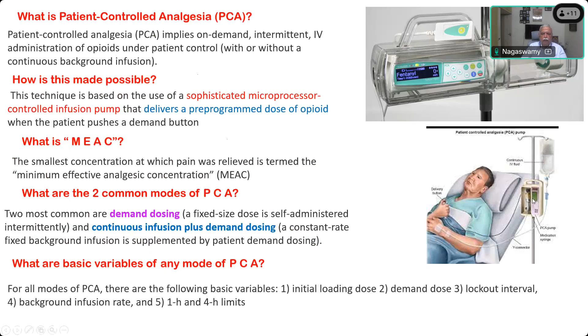What are the basic variables? That is the parameters that you have to include in the mode of PCA. There are five things which you have to think of. One is, what is the initial loading dose? This you have to calculate and then program it into the infusion pump. Then how much every time the demand dose you have to give, and what is the lockout interval, whether it is 15 minutes, 30 minutes or 1 hour, and what should be the background infusion rate, and what are the 1 hour and 4 hour limits. These five parameters have to be included or fed into the machine. So that is why it has got a sophisticated microprocessor controlled infusion pump.